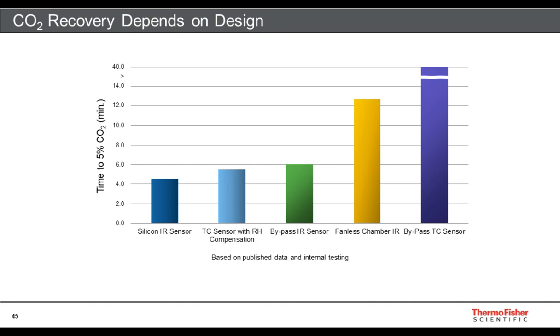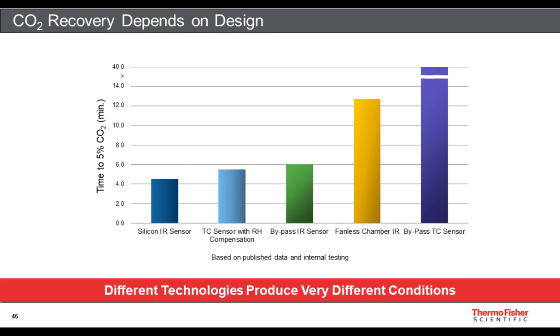A newer technology thermal conductivity sensor, which has relative humidity compensation so that the measurement is no longer dependent on humidity, also recovers quite fast. The green bar indicates a bypass infrared sensor, which is a little bit slower to recover, and this makes sense because this sensor is outside the incubator chamber, and we'll talk about that a little bit later in the talk. If you have an incubator with an IR sensor, but it does not have a circulating fan to speed recovery, you can see that doubles the recovery time. That's the yellow bar. And then finally, if you have an older style thermal conductivity sensor and it's outside the incubator chamber, so it's a bypass sensor, I've actually had to truncate the graph there. So that recovery is 40 minutes from a 30-second door opening. So again, I hope I've demonstrated that different technologies can produce very different conditions, and of course that's going to affect how your cells grow.